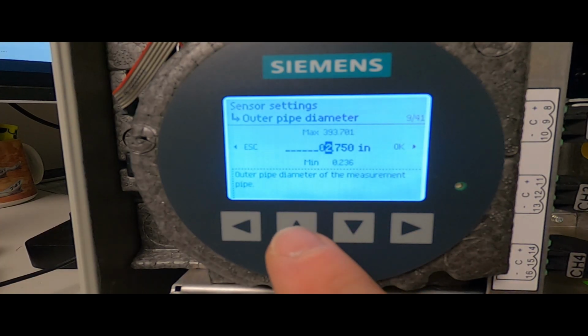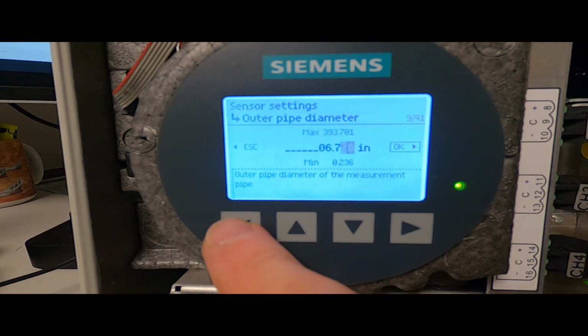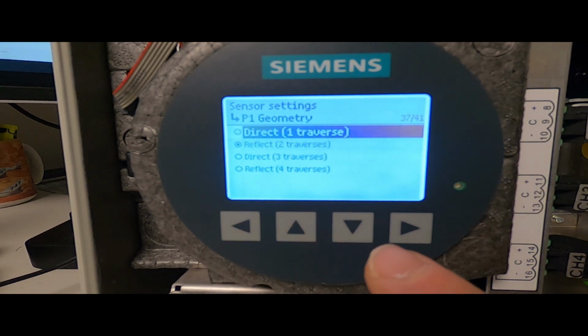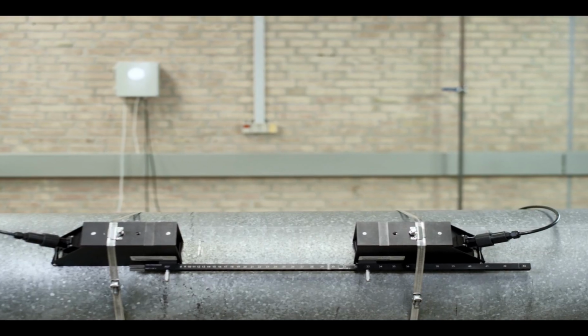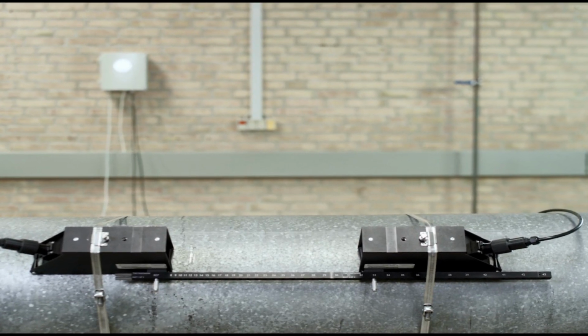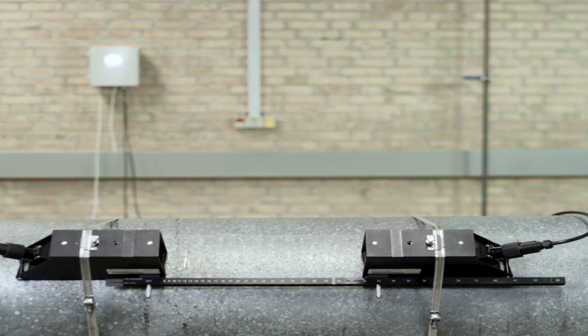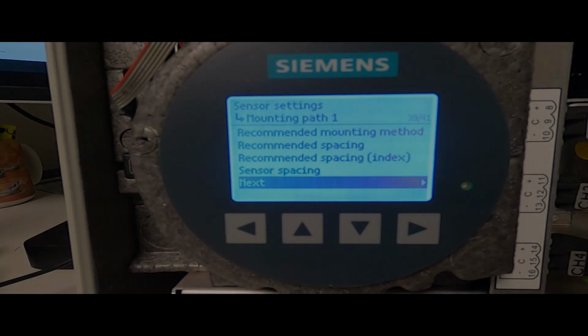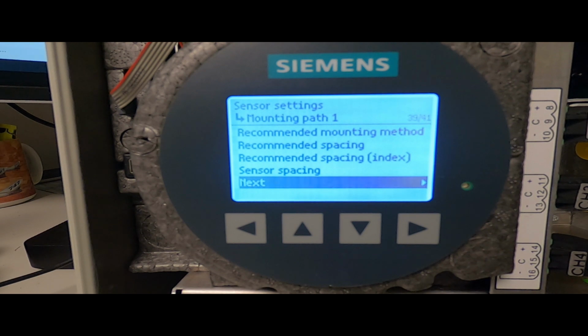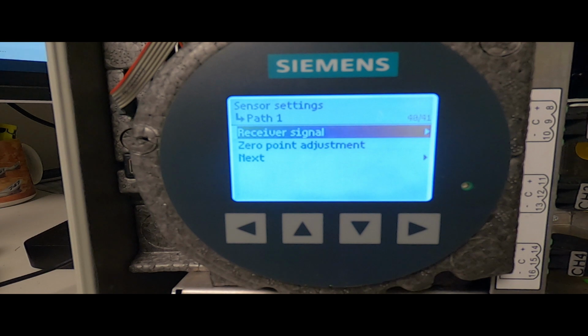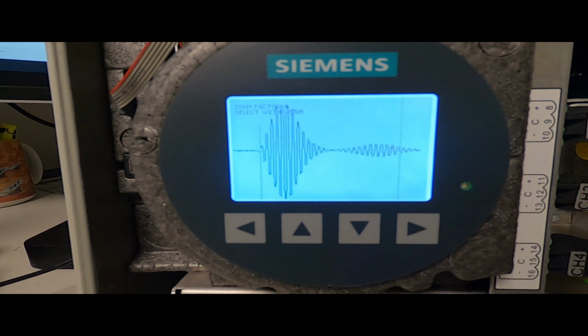The procedure is always the same regardless of pipe size. For liquid applications, simply change the programming to half the pipe diameter and direct mounting. Then leave your sensors right where they were originally installed. That's all you need to do. And now we're ready to proceed. Just go ahead and complete the remainder of your programming steps so that the meter performs the frequency sweep to generate operation. You should now be able to see a receiver signal, which is kind of like the meter's heartbeat.